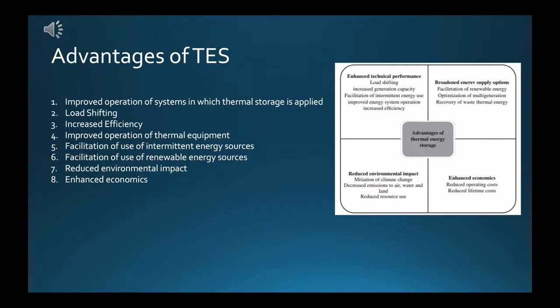TES systems can complement heat pumps for heating or cooling by providing hot or cold reservoirs, thereby improving their efficiencies and performances. A cogeneration plant with TES not following a thermal load can be operated more advantageously, helping overcome the weakness of cogeneration plants, which are generally operated to meet the demands of the connected thermal load, often resulting in excess electric generation during periods of low electricity demand. For load shifting, TES permits energy consumers to shift energy use from high to low demand periods, allowing smaller production units to be installed or increased capacity without additional units.